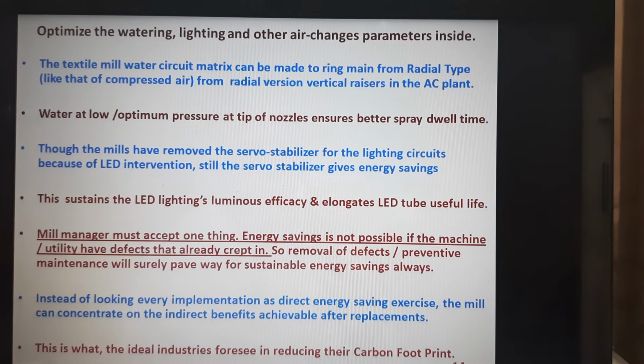Optimizing the water, lighting and air changes parameters decides the energy efficiency at the mill. As I said, the water circuit in the AC plant, the humidification plant, can be made like a ring main circuit. Instead of all the radial type vertical risers standing alone, they can be combined as a T connection and made into a ring main circuit, so that the overall water pressure distribution can be reduced, and the spray dwell time of the water inside the mist eliminator can be increased.